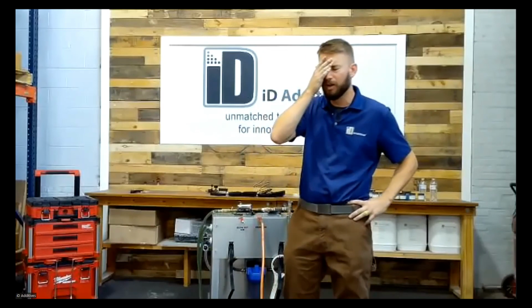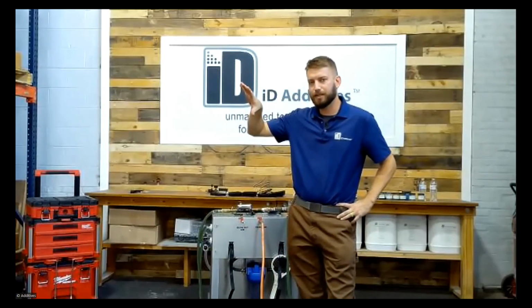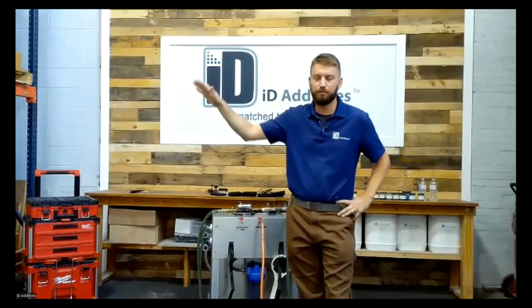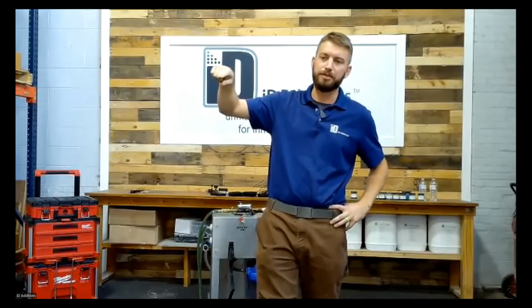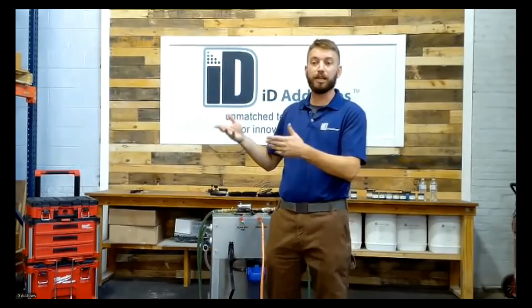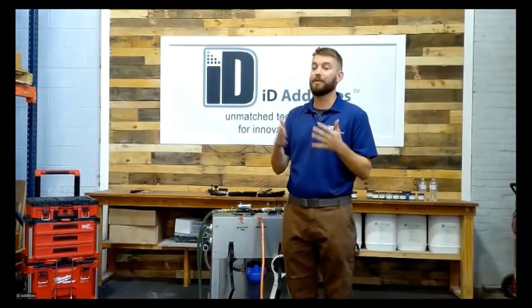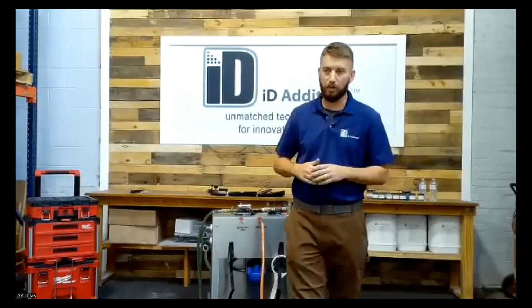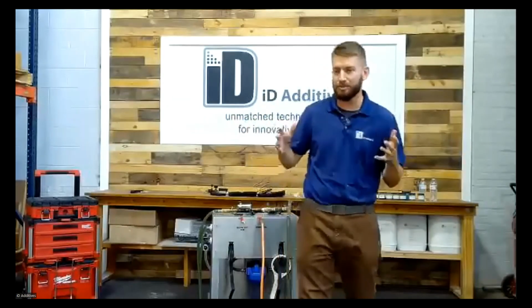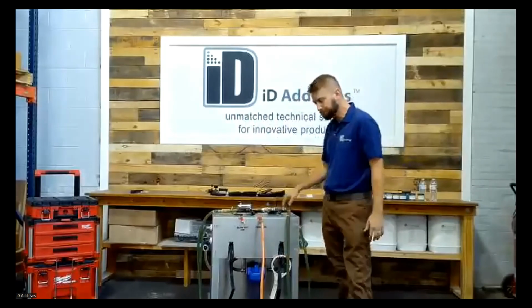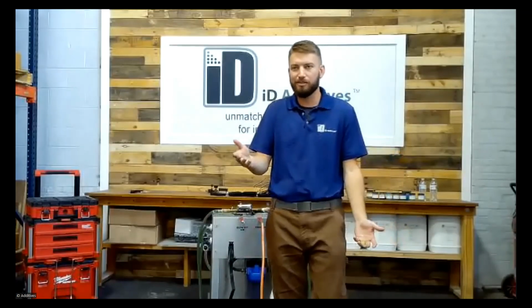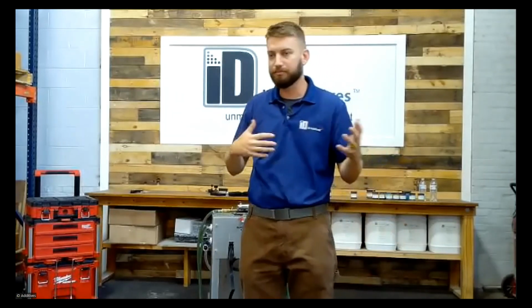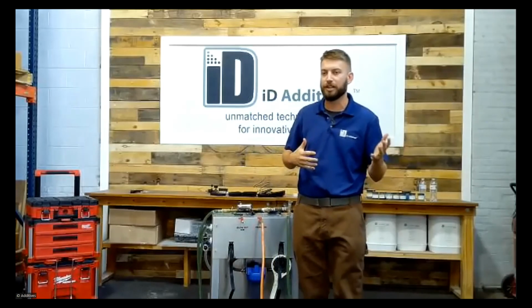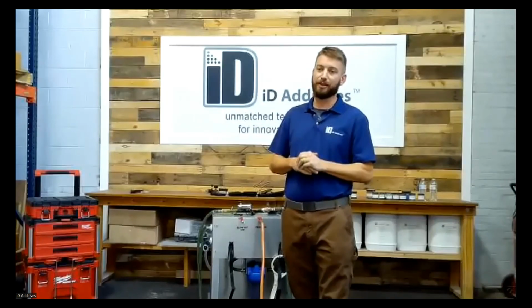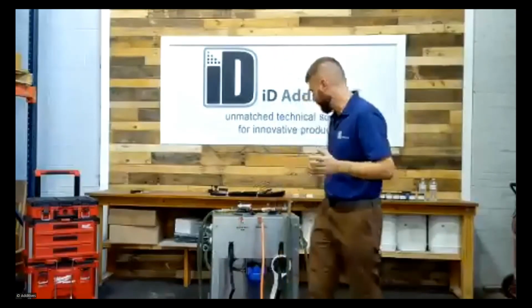I wish I would have posted a photo. I recently worked with an extrusion manufacturer that had a sidecar with five heat exchangers, four for the rolls and one as a backup. We plumbed in quick fittings. Even though heat exchangers don't block up that often, depending on your area and water quality, let's say your heat exchanger blocks up every 14 months. You throw on these quick connects like I did here, and then every 10 months or so, hook up and flush for an hour. That way the heat exchanger doesn't crash on you. They're expensive and on back order right now like most things are, so if you can do anything to prevent that, it's worth it.